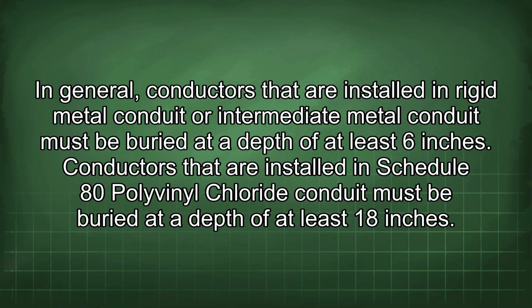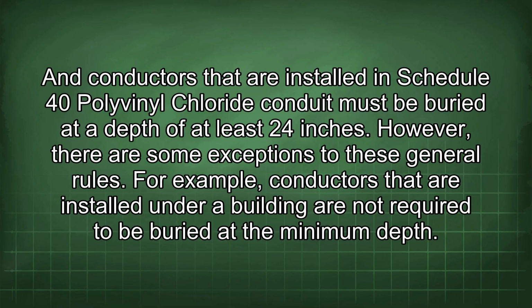Conductors that are installed in Schedule 80 polyvinyl chloride conduit must be buried at a depth of at least 18 inches. And conductors that are installed in Schedule 40 polyvinyl chloride conduit must be buried at a depth of at least 24 inches. However, there are some exceptions to these general rules. For example, conductors that are installed under a building are not required to be buried at the minimum depth.